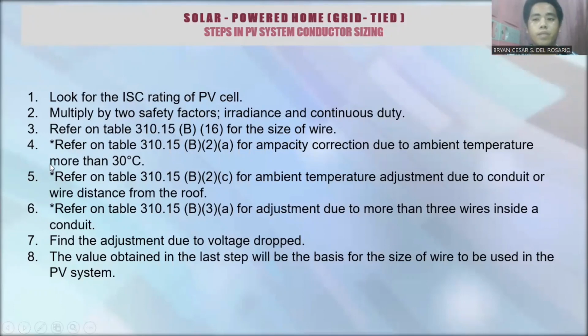Numbers 4 and 5 are needed only when required. When it needs to be computed, refer to table 310.15(B)(2)(a) for ampacity correction due to ambient temperature more than 30 degrees Celsius, and table 310.15(B)(2)(c) for ambient temperature adjustment due to conduit or wire distance from the roof.